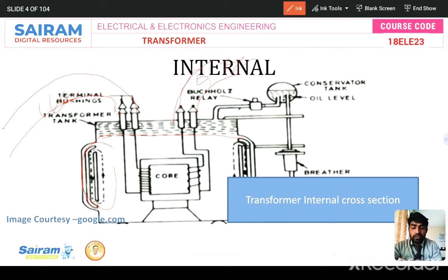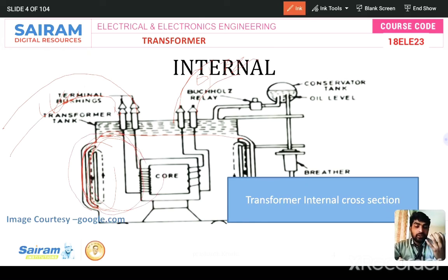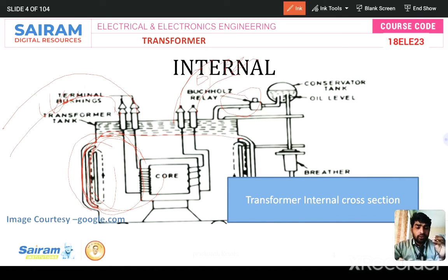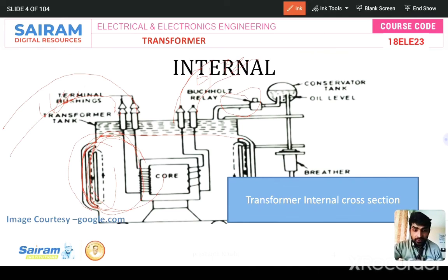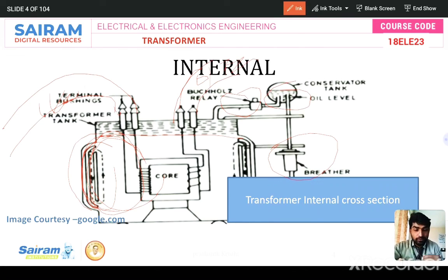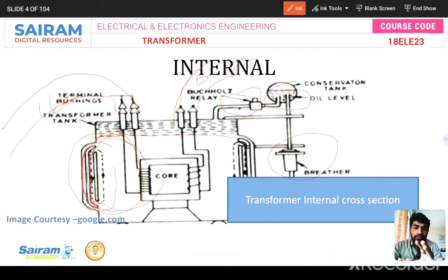When current flows through the transformer winding, heat is produced at the top, then it recycles for uniform cooling. If moisture contents or dust particles are present, or if transformer windings get a spark or fault, the Buchholz relay detects that part, sends a signal to the circuit breaker, and further damage to the transformer is avoided. There is also a breather — for sucking moisture content and dust particles from inside the transformer tank oil. The oil level conservator is for filling the oil when evaporation occurs due to heat. This is the constructional internal cross-section of a transformer.